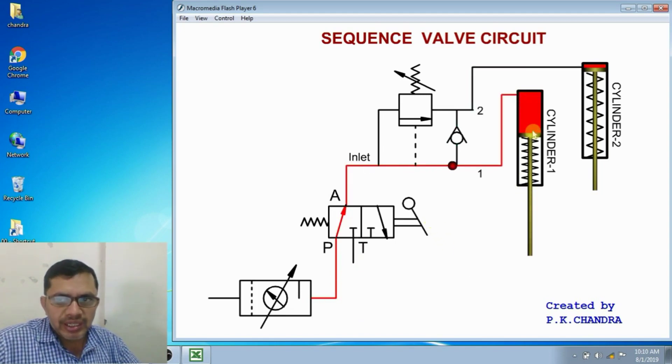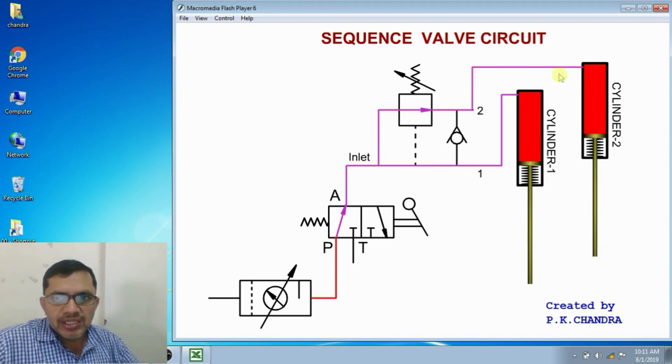In the cylinder, 1 is extending. Once the extension is completed, pressure in the line will increase. And due to which, the sequence valve will open so that the fluid flows to the second cylinder. Increase in pressure in the line causes the sequence valve to open so that fluid can flow to second cylinder.